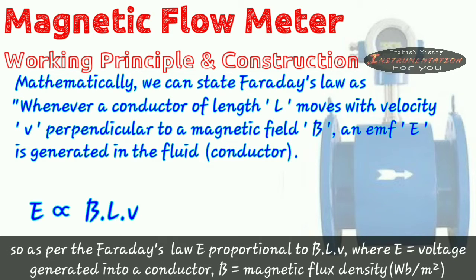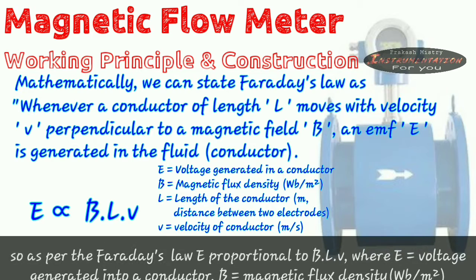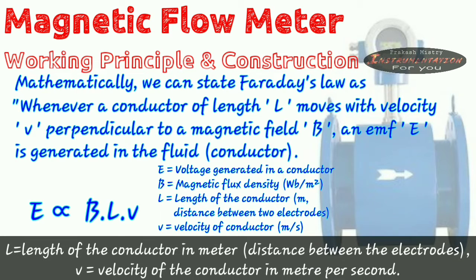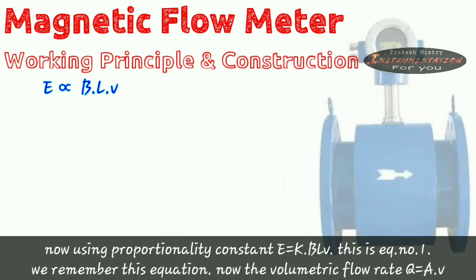So as per Faraday's law, E proportional to BLV. Where E is equal to voltage generated in the conductor. B is equal to magnetic flux density in Weber per meter square. L is equal to length of the conductor in meter, distance between the electrodes. V is equal to velocity of the conductor in meter per second. Now using proportionality constant, E is equal to K into BLV. This is equation number one. We remember this equation.